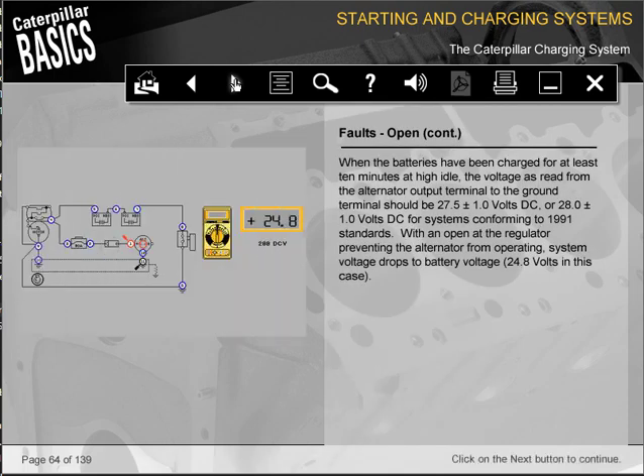When the batteries have been charged for at least 10 minutes at high idle, the voltage as read from the alternator output terminal to the ground terminal should be 27.5 plus or minus 1.0 volts DC, or 28.0 plus or minus 1.0 volts DC for systems conforming to 1991 standards. With an open at the regulator preventing the alternator from operating, system voltage drops to battery voltage, 24.8 volts in this case.